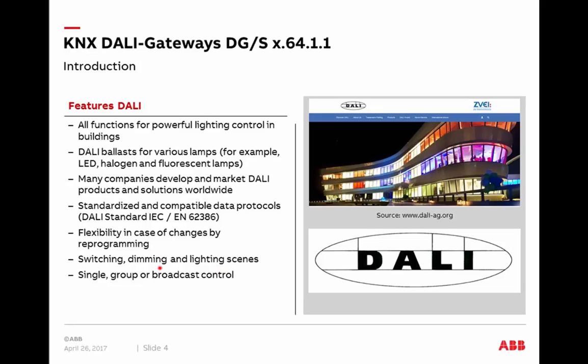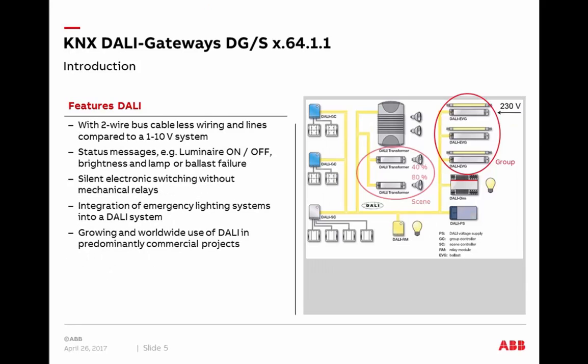On the right you see a DALI standalone system based on a two-wire control cable. All DALI devices — including DALI group and scene controllers to connect conventional push buttons — and on the other side typical DALI ballasts for different kinds of lamps are linked together with a two-wire bus cable. Together with power connected to each lamp, you can create a light system with light scenes. Groups can be assigned to sensors — a very flexible, typical system for lighting control.